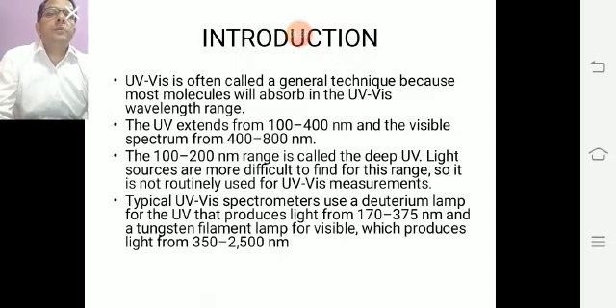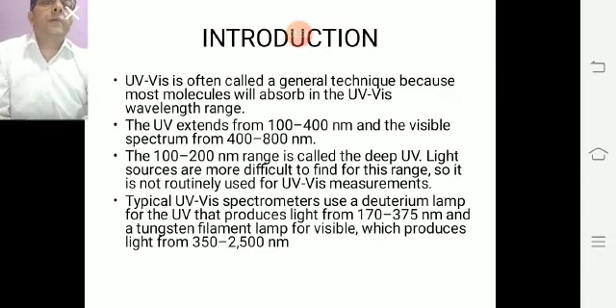Typical UV-visible spectrophotometers use a deuterium lamp for UV, which produces light from 170 to 375 nm, and a tungsten filament lamp for visible, which produces light from 350 to 2500 nm.